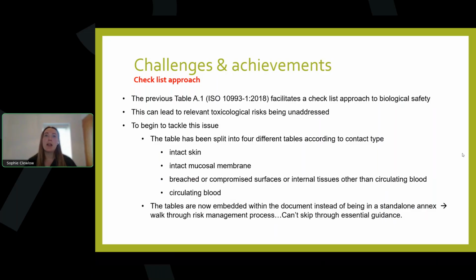So to help align more closely with the risk management approach and reduce that possibility of missing key information and guidance, the categorization tables have now been integrated within the document. And you'll note there that I said tables, plural, and this is because the table that we all know so well has now been split into 4 separate tables according to contact type. So that's intact skin, intact mucosal membrane, breached or compromised surfaces or internal tissues other than circulating blood, and then circulating blood. So many of those contact types will be familiar to you from the subcategories of contact that were in the 2018 tables.